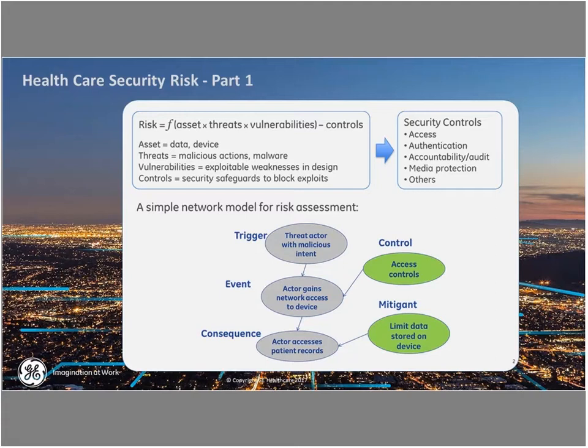So you have to start with somebody that has malicious intent here. The event would be that that actor gains network access to the device, and then the consequence is access to those patient records. We can apply control to minimize the likelihood that that actor is going to be able to gain access to the device by, as an example, putting in place some access controls. We can also mitigate the impact of that consequence if it were to occur by limiting the amount of data stored on the device. So when we're designing a device, we want to look both at access controls that can help minimize the likelihood that a bad event will occur, and we also want to look at mitigations so that if something bad does occur, we have minimized the impact.